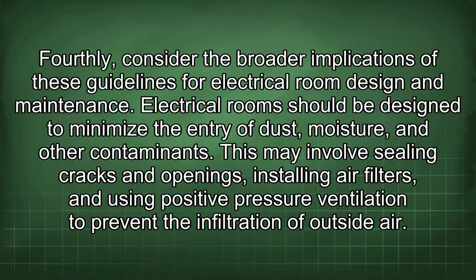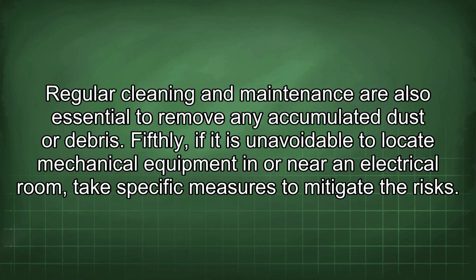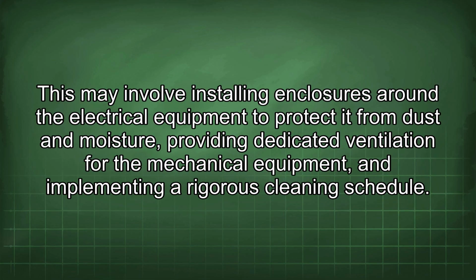Fourthly, consider the broader implications of these guidelines for electrical room design and maintenance. Electrical rooms should be designed to minimize the entry of dust, moisture, and other contaminants. This may involve sealing cracks and openings, installing air filters, and using positive pressure ventilation to prevent the infiltration of outside air. Regular cleaning and maintenance are also essential to remove any accumulated dust or debris. Fifthly, if it is unavoidable to locate mechanical equipment in or near an electrical room, take specific measures to mitigate the risks. This may involve installing enclosures around the electrical equipment to protect it from dust and moisture, providing dedicated ventilation for the mechanical equipment, and implementing a rigorous cleaning schedule.